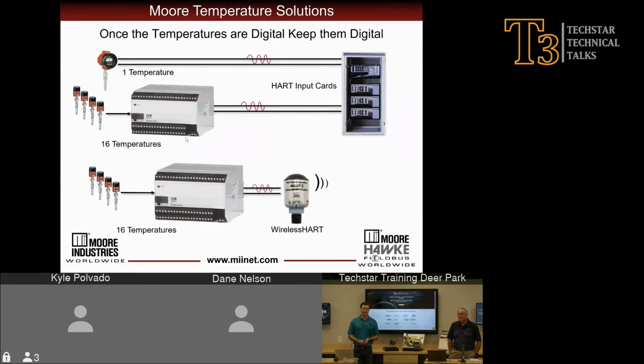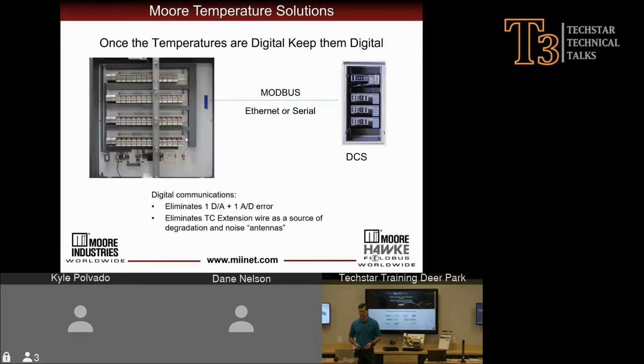One other way that we can reduce the amount of uncertainty in our temperature sensor measurement is by converting that low-level temperature millivolt signal and resistance signal to a high-level analog signal or a digital signal. So once you convert your temperature to a digital signal, we highly recommend keeping that signal digital because of the amount of information available on digital protocols and the speeds.